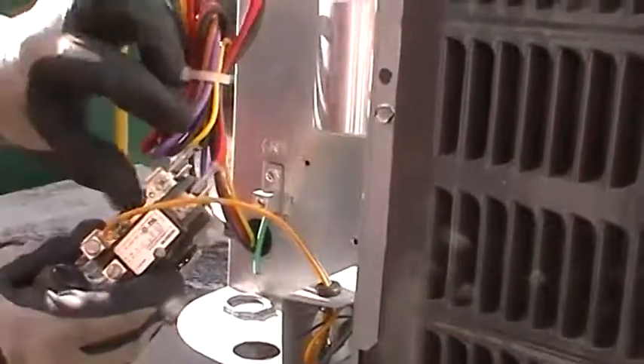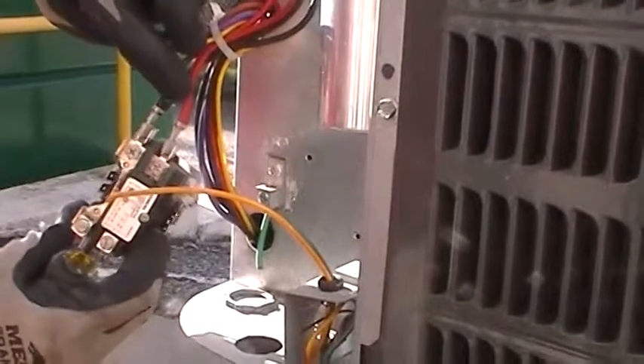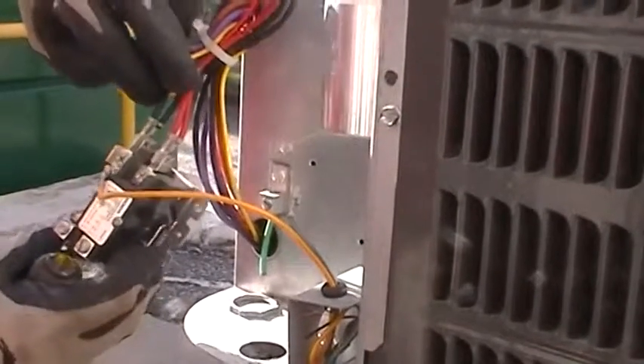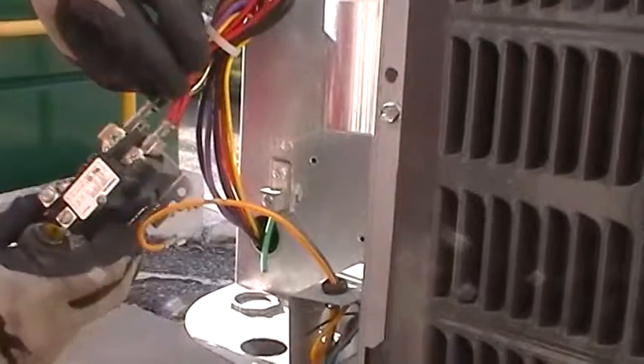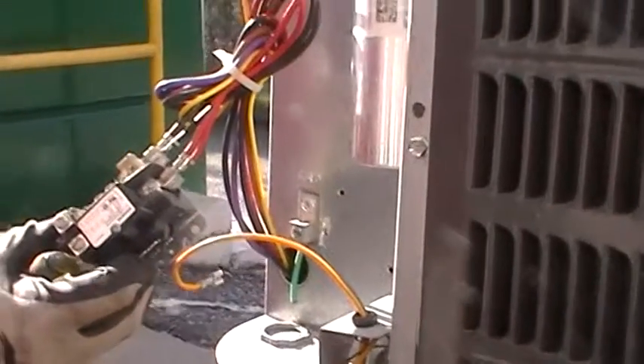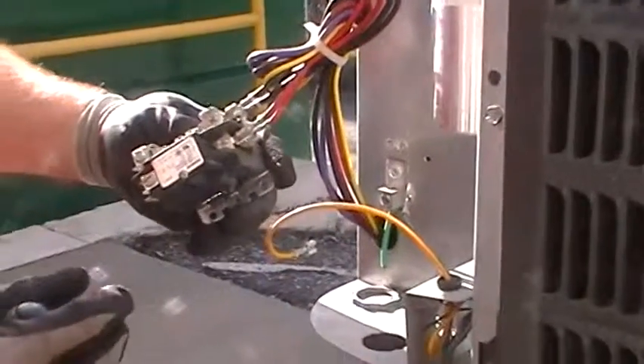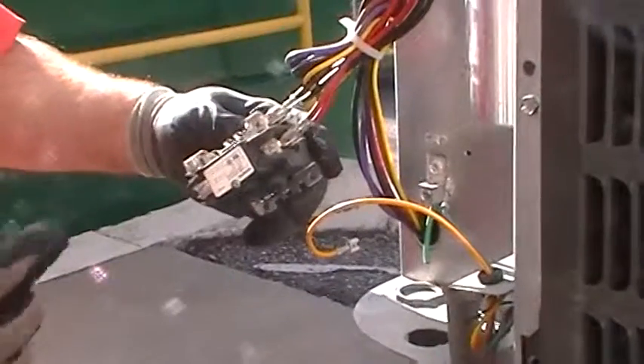If you'll notice, I left the load side of the contactor still wired up. It's not under the lugs, just quick connects, so I won't get my wiring connections confused when I set my new one in there and change the wires over.